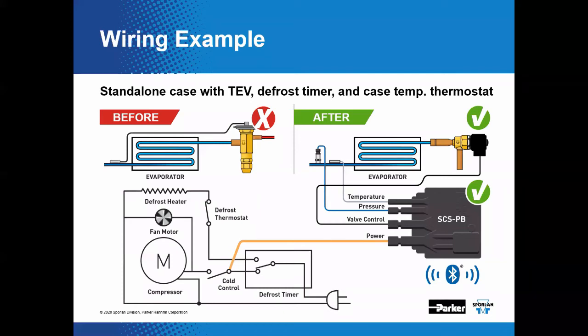In this example, the power of the controller is wired to a defrost timer. Now, that's not saying that you have to wire it there. I'm just showing that in this solution, okay? The reason for that is once the unit goes into defrost, the controller itself would shut down, and since it's using a pulse width expansion valve, the valve will actually close on power loss. Therefore, you will have a positive shutoff on your evaporator. As I covered before, the setup is extremely simple, and the user will be able to select the refrigerant type, the pressure transducer type, and the superheat target, and that is all the setup that is required.